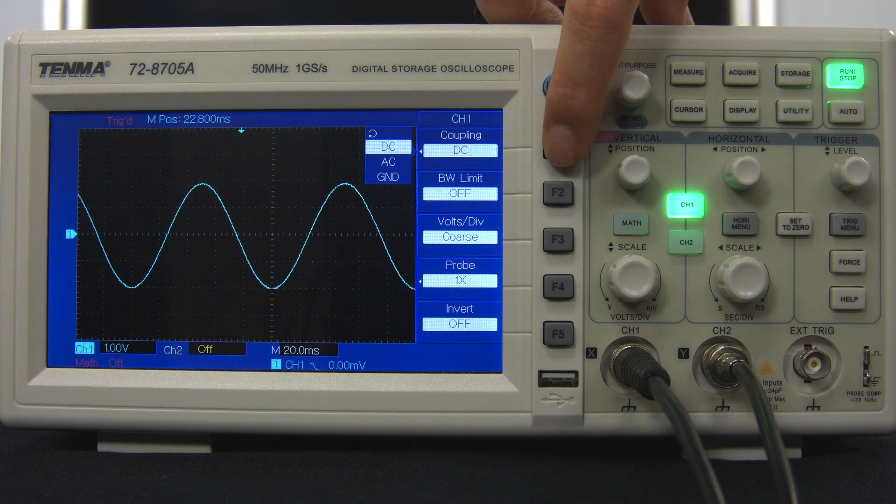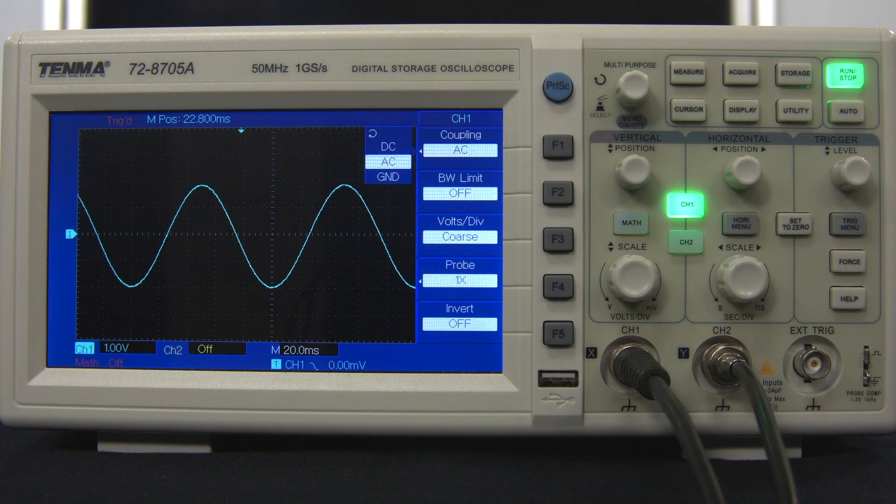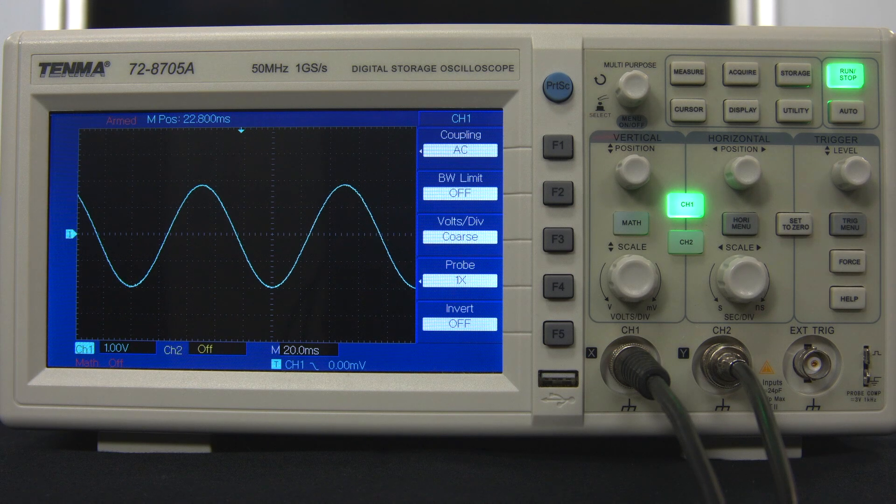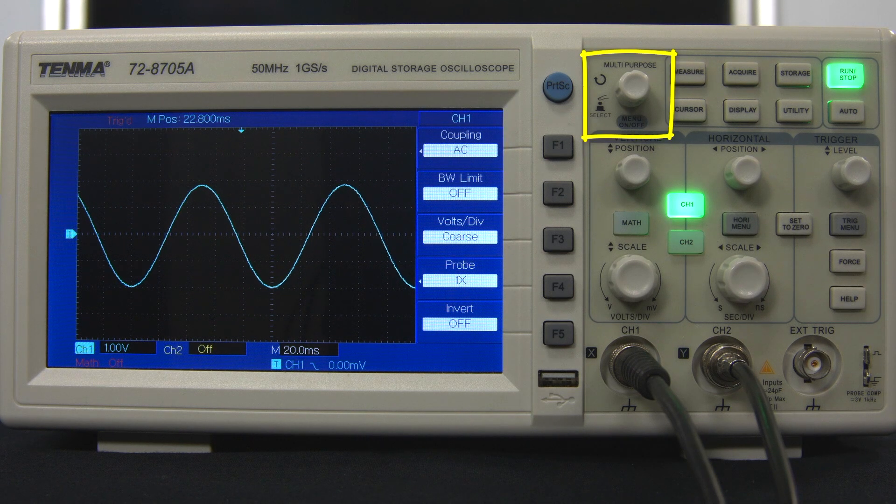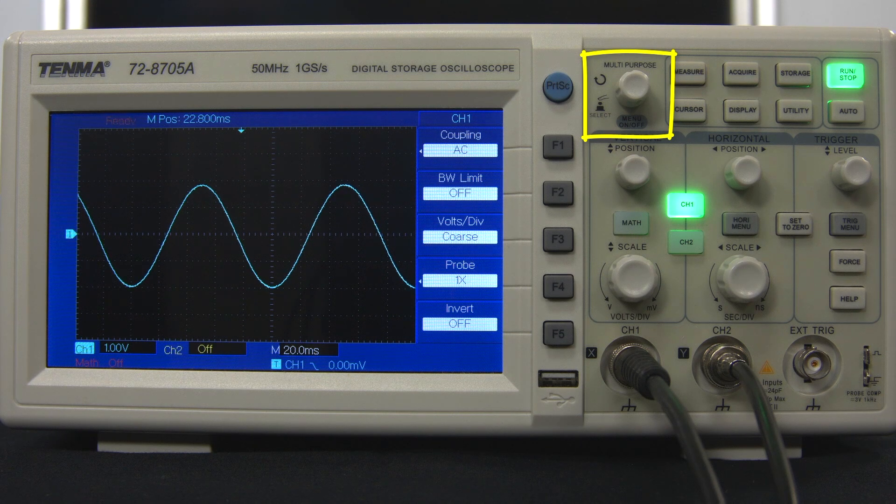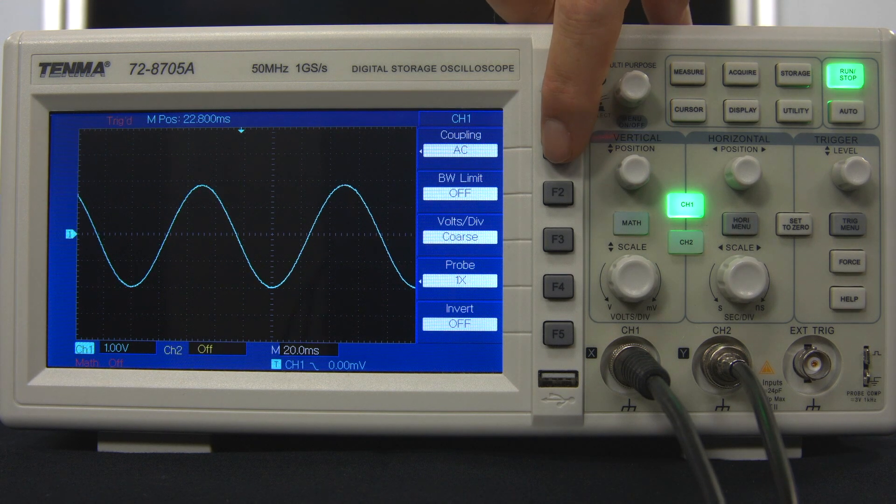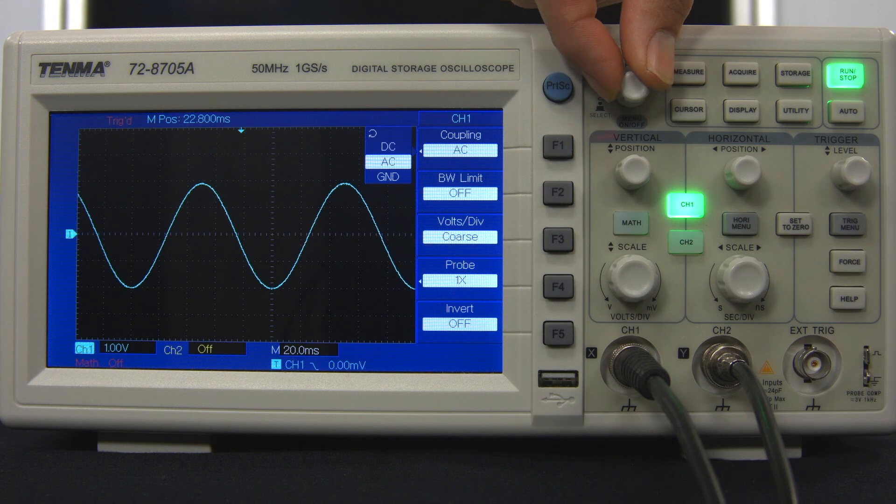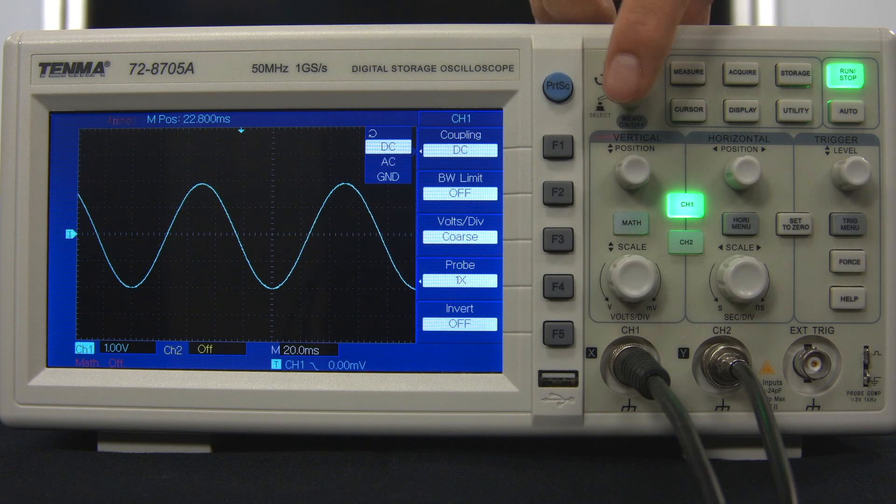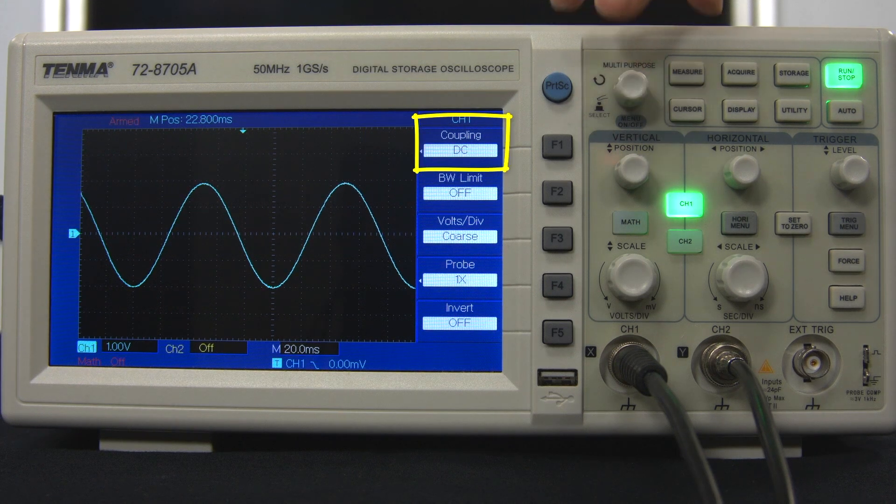In this case, a submenu of options appears. Continuing to press the F1 button scrolls through this submenu, and waiting a few seconds allows the selected option to become active. In this case, the coupling has been changed to AC. Another way to use the submenus is with the multipurpose knob at the top of the control section. Once the submenu is visible, turning the multipurpose knob scrolls through the options. Rather than wait a few seconds, the desired selection can be chosen by pressing the multipurpose knob. In this case, coupling has been changed back to DC.